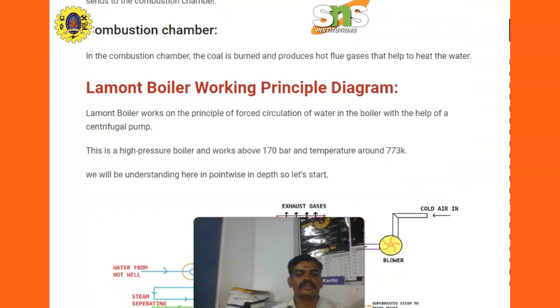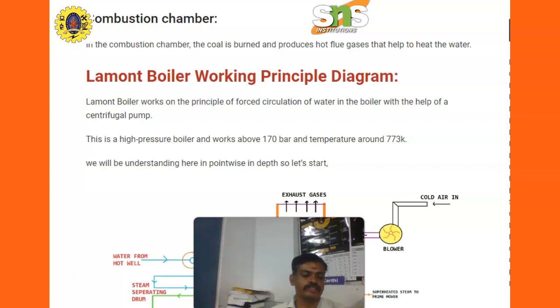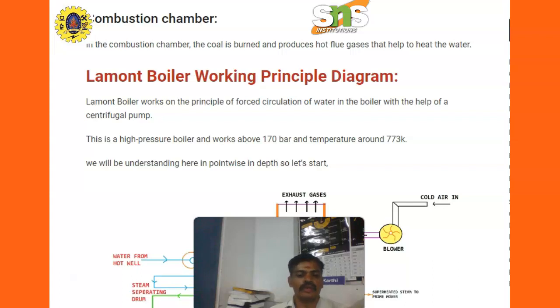Next is the Lamont boiler working principle. The Lamont boiler working principle involves forced circulation of water in the boiler with the help of a centrifugal pump. This is a high pressure boiler and works above 170 bar at a temperature around 700 Kelvins and above.